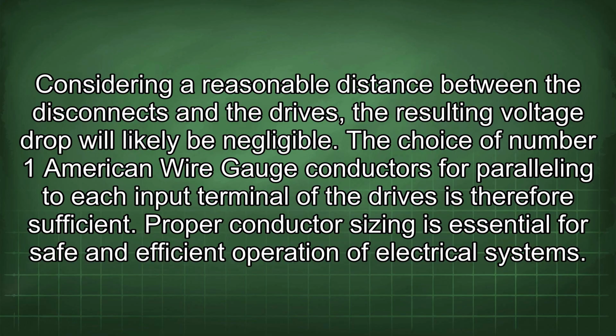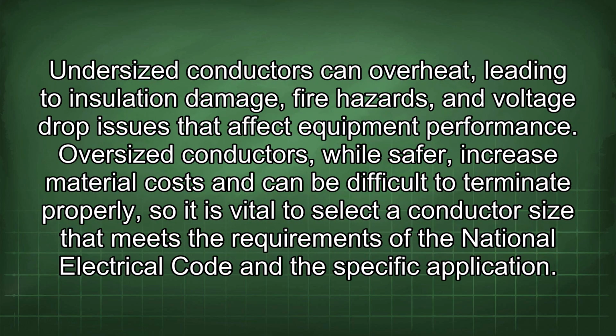The choice of number 1 American wire gauge conductors for paralleling to each input terminal of the drives is therefore sufficient. Proper conductor sizing is essential for safe and efficient operation of electrical systems. Undersized conductors can overheat, leading to insulation damage, fire hazards, and voltage drop issues that affect equipment performance. Oversized conductors, while safer, increase material costs and can be difficult to terminate properly, so it is vital to select a conductor size that meets the requirements of the National Electrical Code in the specific application.